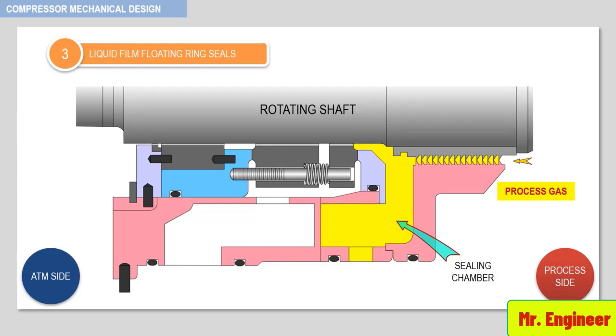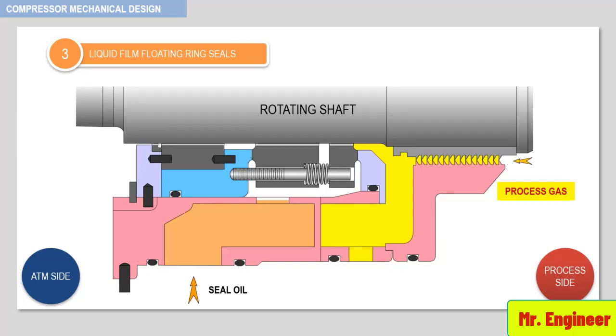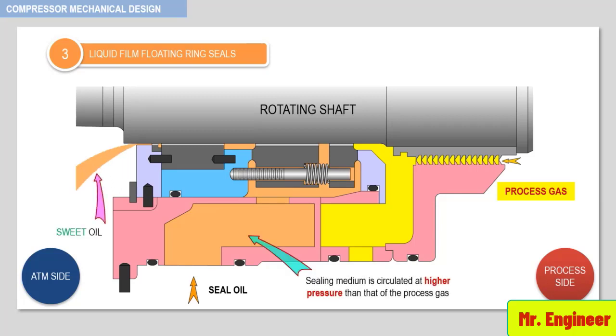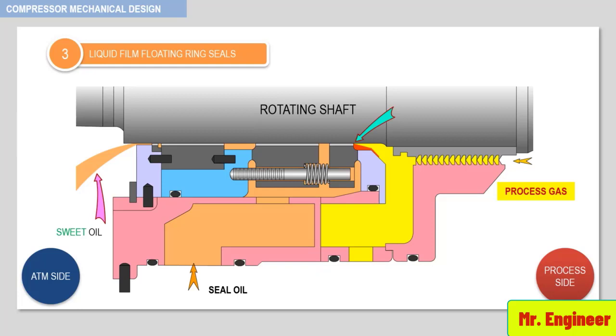But before the entry of process gas, the sealing medium is circulated continuously at a higher pressure than that of the gas being sealed. Most of the sealing oil flows across the seal rings toward the atmospheric side and is then recovered. This oil is called sweet oil. The oil at higher pressure also flows across the inner seal ring and restricts the flow of process gas to the atmosphere.